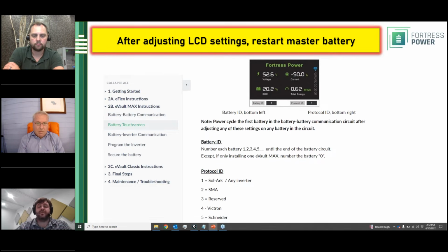The issue with our batteries is they're simple enough to set up in the field and power on without looking at the manual. But if you don't look at it, there are a couple of gotchas—like this protocol ID, or the fact that after you program all the eVault Max LCD screens, you need to power cycle the master battery—that you won't catch unless you read the inverter guide or the longer product manual.